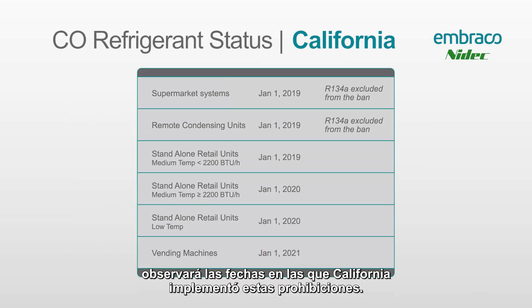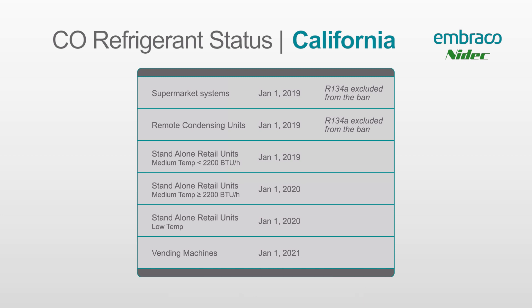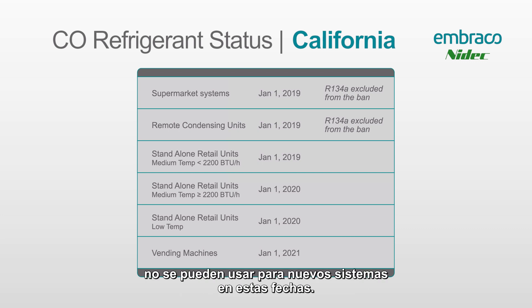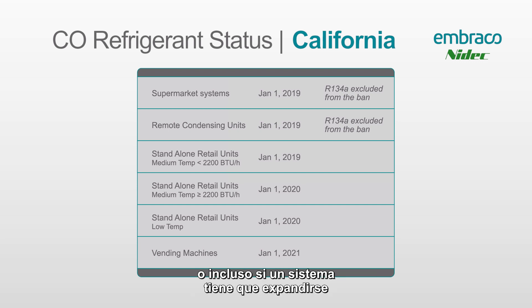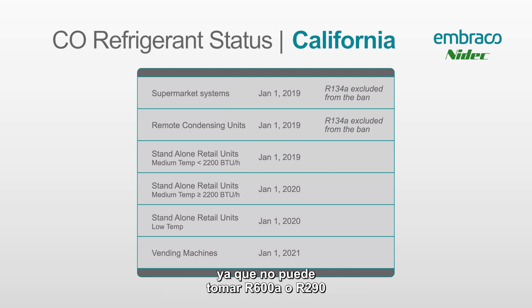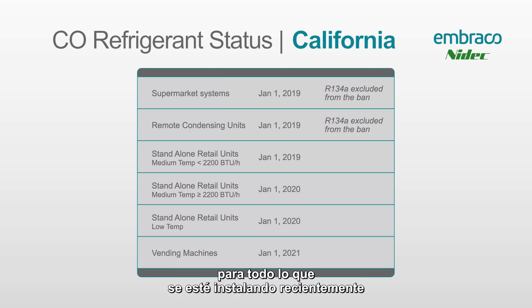If you look at the chart, it'll show the dates of when California implemented these bans. They first started with the top three categories, such as supermarket systems, on January 1st of 2019, and the final ban will be vending machines on January 1st of 2021. What this means is all these gases cannot be used for new systems by these dates. A new system means that if a system is brand new or even if a system has to be expanded and the refrigerant charge is changed, they can no longer use any of these banned gases. This largely means new equipment, since you can't take R600A or R290 and retrofit it into old equipment.